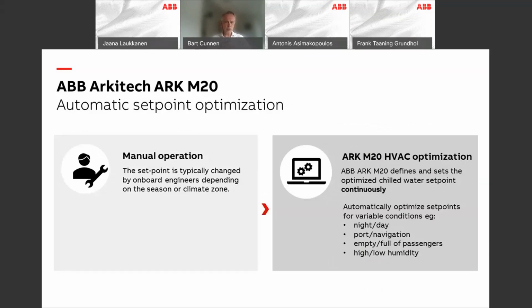Our system is a retrofit solution, looking at vessels up to 20, 25 years old maximum, up to vessels that are fully new. Older vessels are manual or semi-manual operated, and our system enables continuous optimization of chiller set points. We look at night and day situation, port or navigation, how full the vessel is, humidity, and other variables.